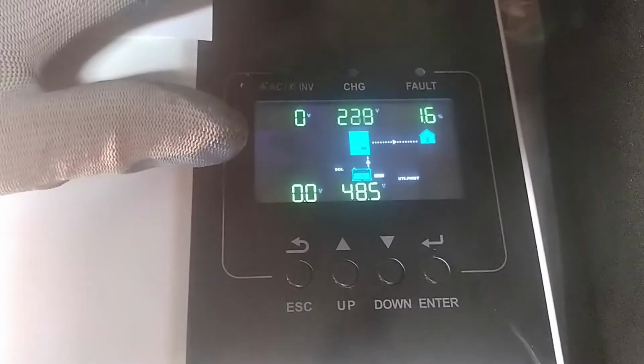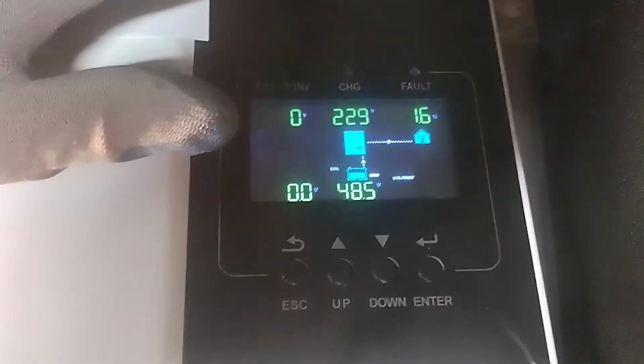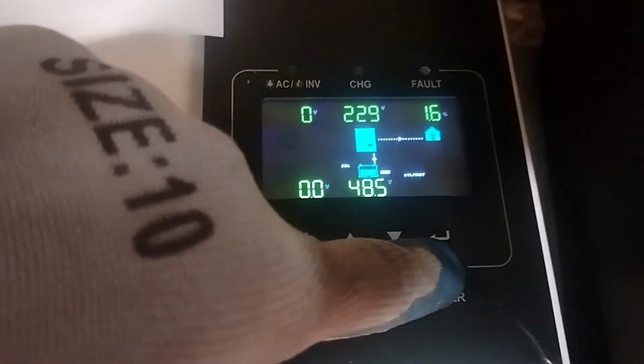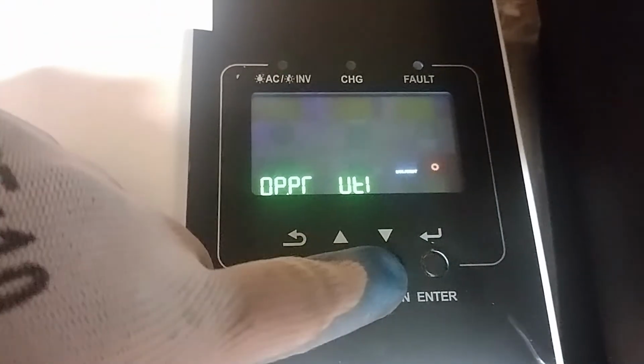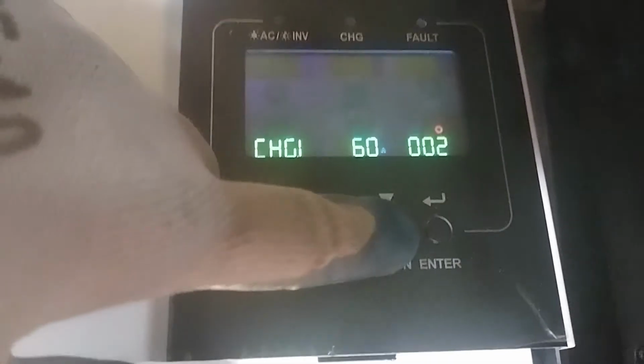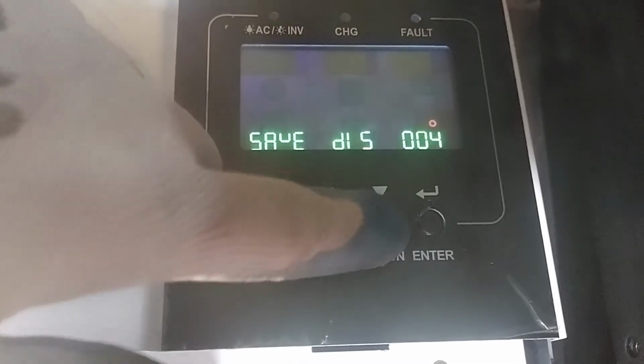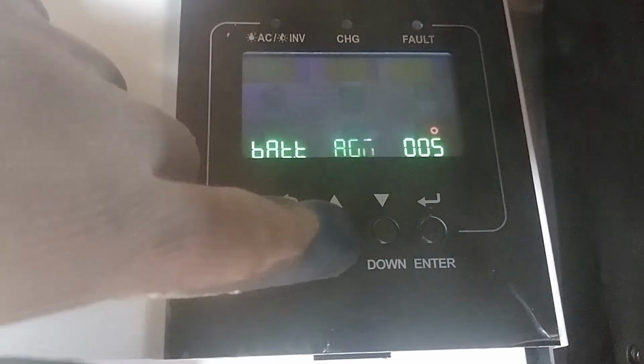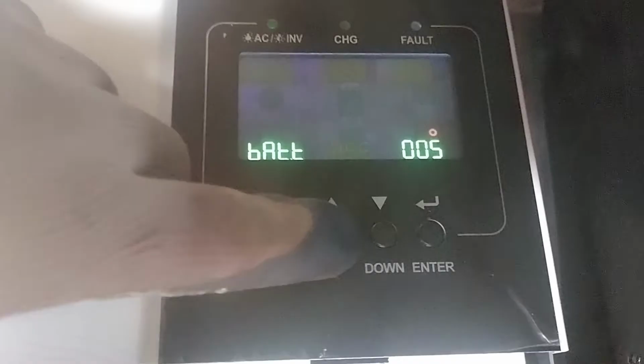So in that case, we want this to work with no error. Error 4 is low battery, and error 20 is a communication error. So we want to trick the system - as you can see, the charging current is 60 amps, which is for AGM. In this case, we want to trick the inverter into accepting this lithium protocol.